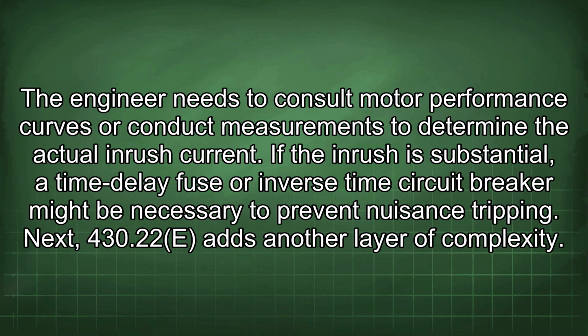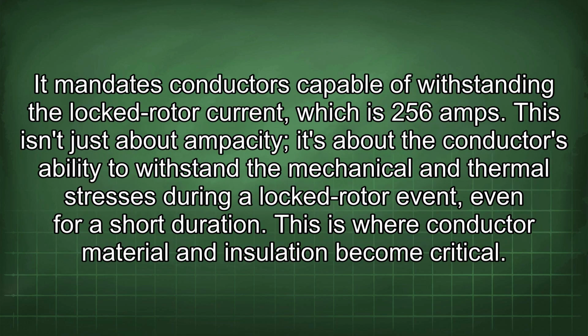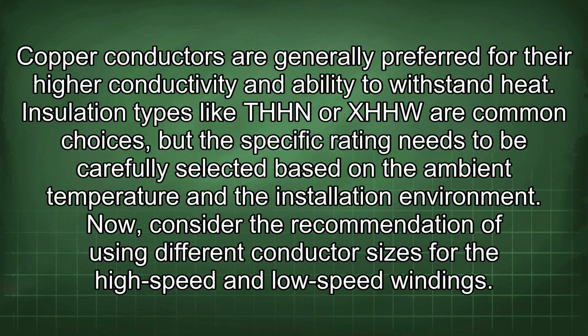Next, 430.22e adds another layer of complexity. It mandates conductors capable of withstanding the locked rotor current, which is 256 amps. This isn't just about ampacity, it's about the conductor's ability to withstand the mechanical and thermal stresses during a locked rotor event, even for a short duration. This is where conductor material and insulation become critical. Copper conductors are generally preferred for their higher conductivity and ability to withstand heat. Insulation types like THHN or XHHW are common choices, but the specific rating needs to be carefully selected based on the ambient temperature and the installation environment.